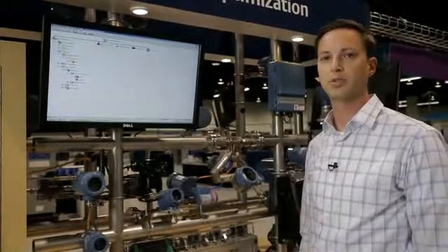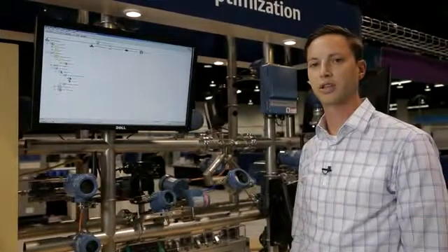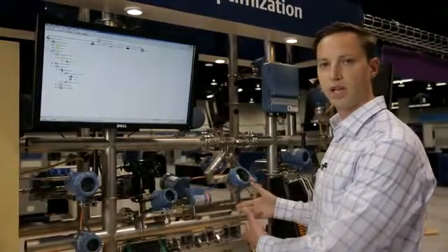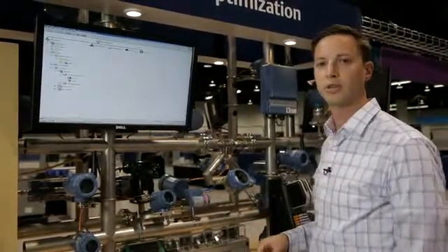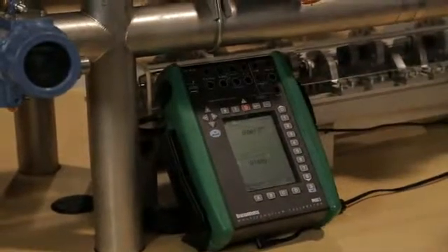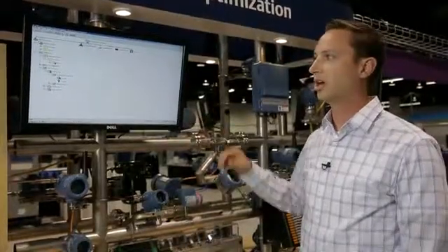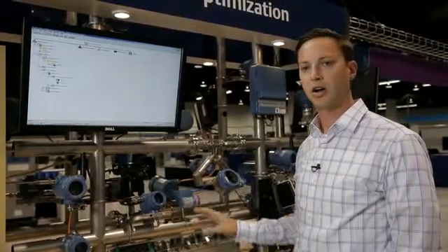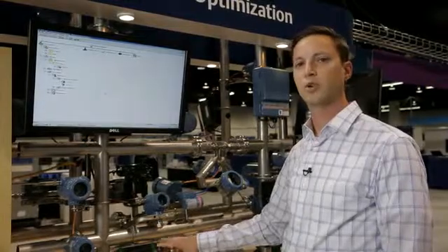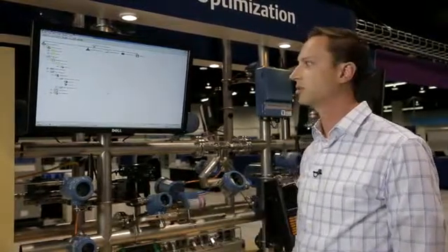Then the next step is where the technician or whoever is working on the devices will go out with the calibrator to the devices, and do the actual calibrations at the devices. They'll bring it back to the workbench or wherever they started this process with the computer, simply upload that data back into Device Manager, and all of the information that was captured from the devices with the Smart Documenting Calibrator will be brought into AMS Device Manager.